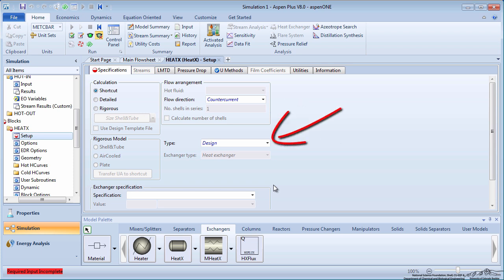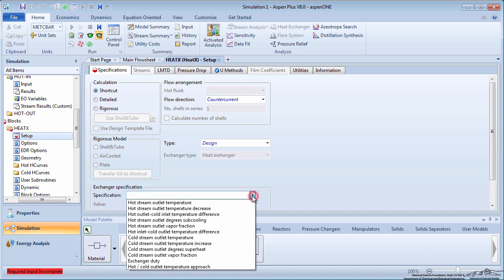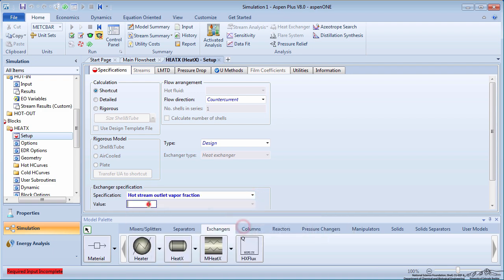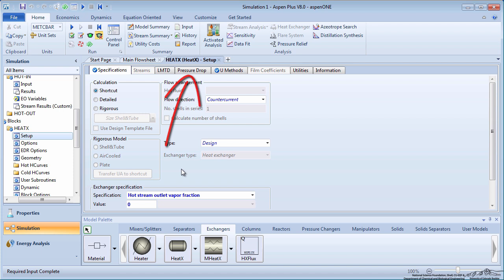Input the type as design, and under the exchanger specification block, specify the hot stream outlet vapor fraction as zero. Assume there is no pressure drop in the heat exchanger and that the U value that Aspen calculates is sufficient.